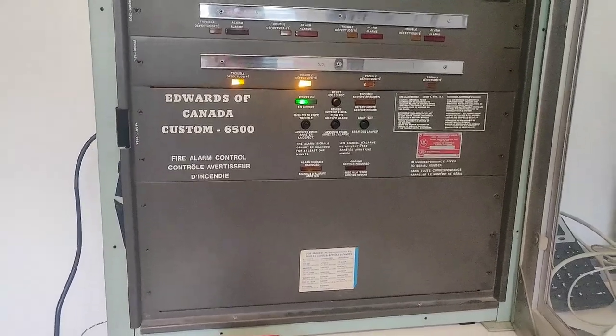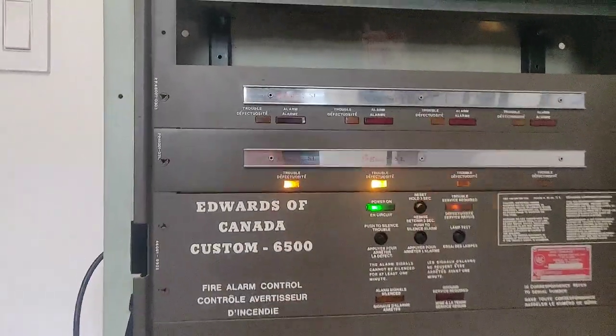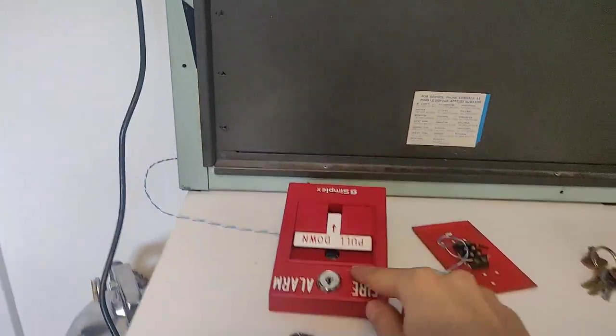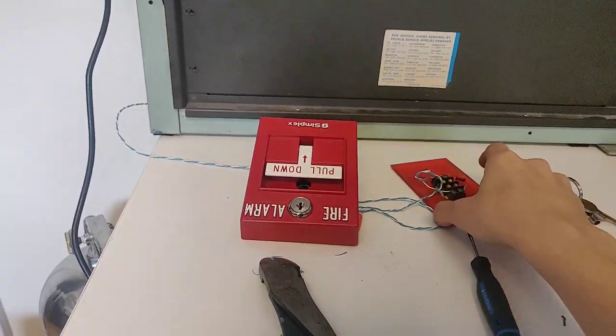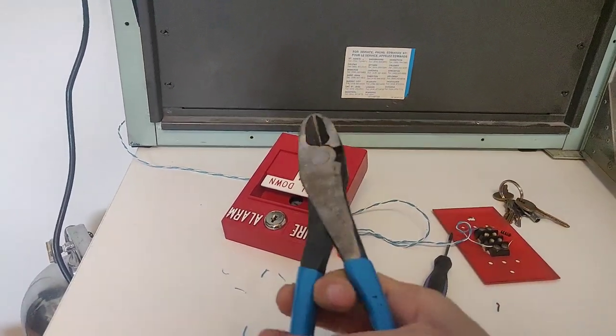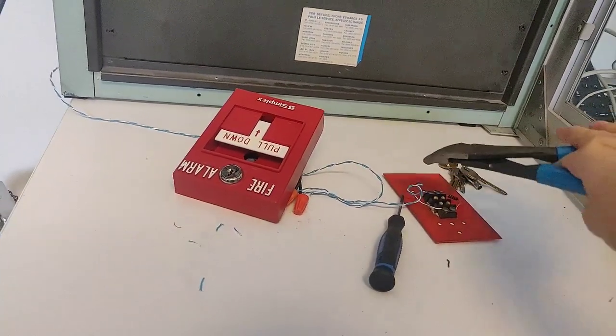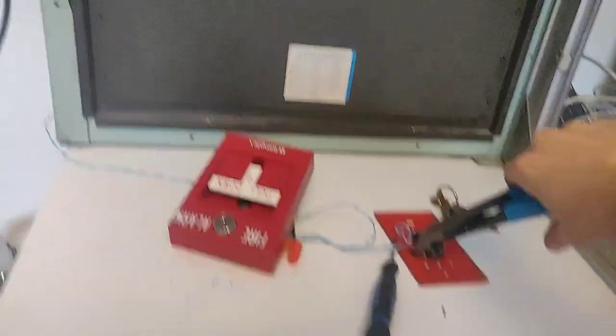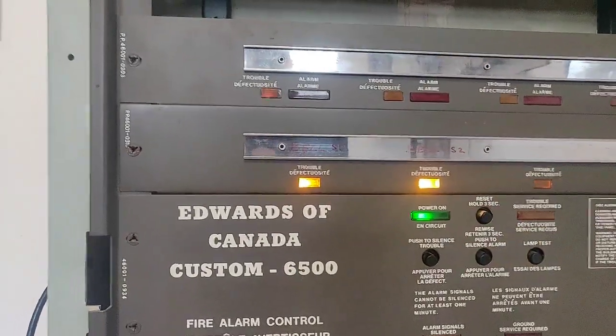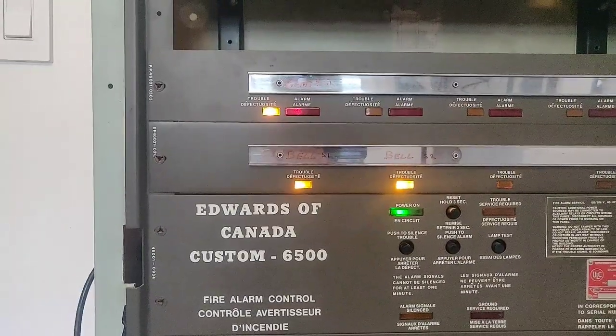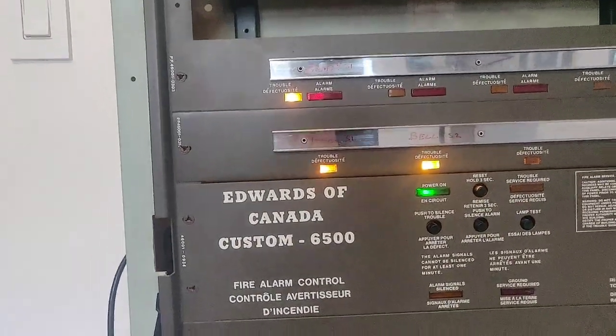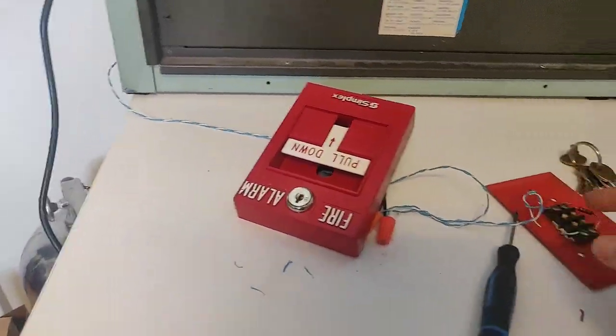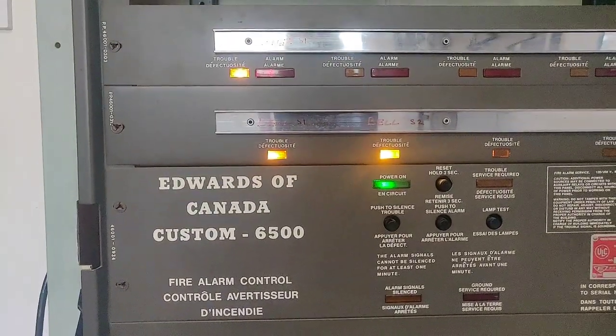So allow me here to demonstrate the supervision. So this is our zone one. Our zone one is wired to the pull station as we saw earlier. Here's our end of line plate. Here's our wiring. I'm going to take this pair of wire cutters and I'm simply going to cut one of these wires. It doesn't matter which one anywhere along the loop. Watch what happens. There you go. See, it's in trouble. Notice I've cut this wire. Anywhere along the wire, anywhere along the circuit, either wire, if it gets broken that trouble light will come on.